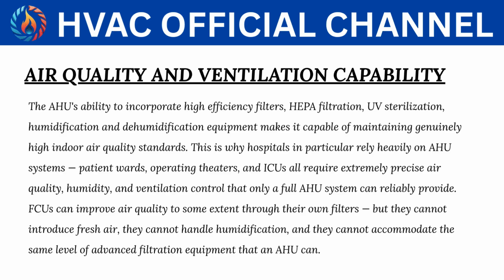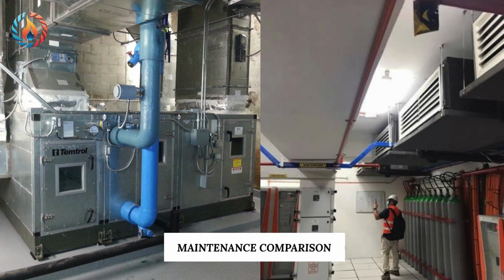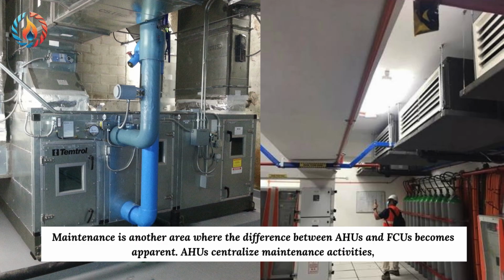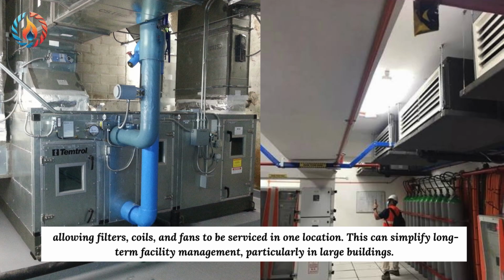FCUs can improve air quality to some extent through their own filters, but they cannot introduce fresh air, they cannot handle humidification, and they cannot accommodate the same level of advanced filtration equipment that an AHU can. Maintenance comparison. Maintenance is another area where the difference between AHUs and FCUs becomes apparent. AHUs centralize maintenance activities, allowing filters, coils, and fans to be serviced in one location. This can simplify long-term facility management, particularly in large buildings.